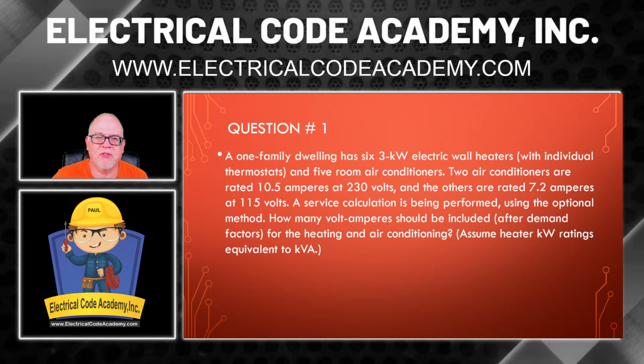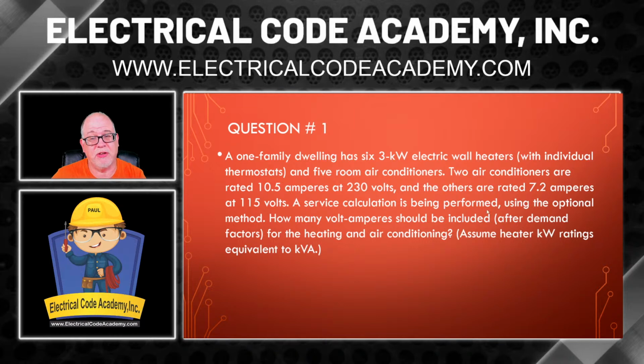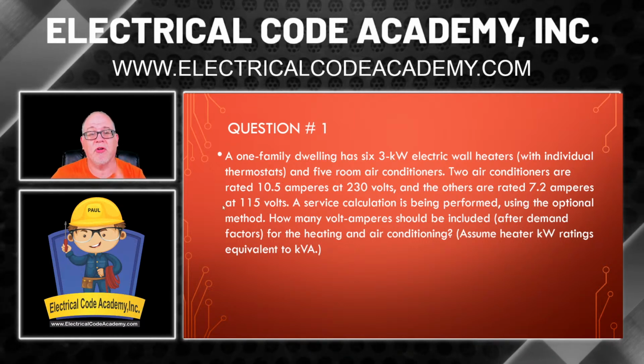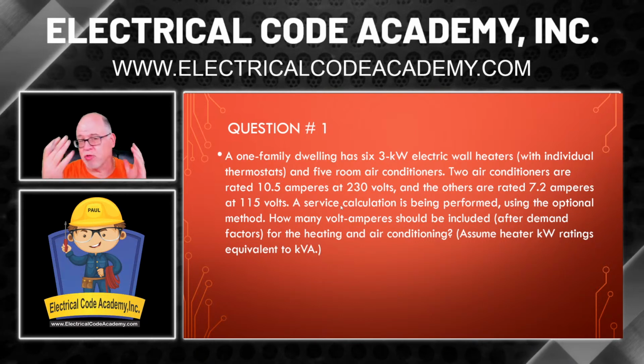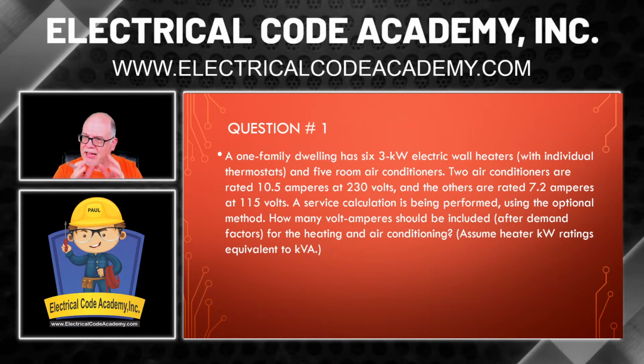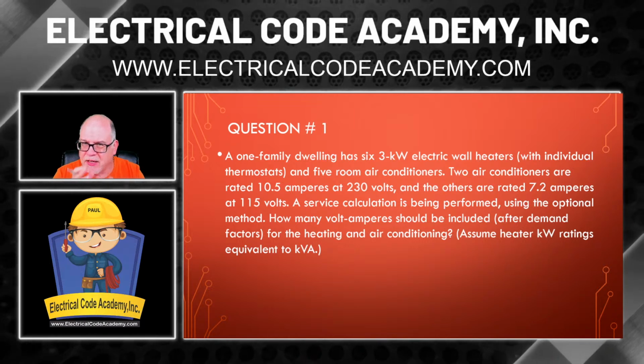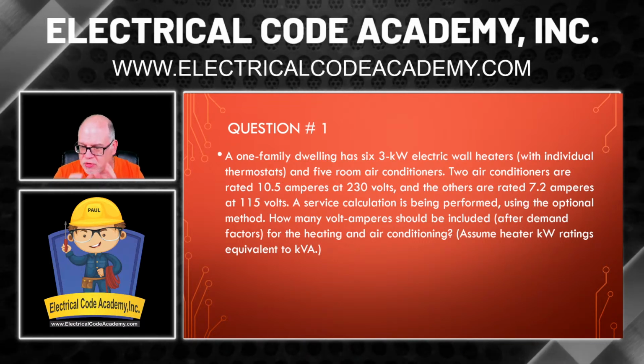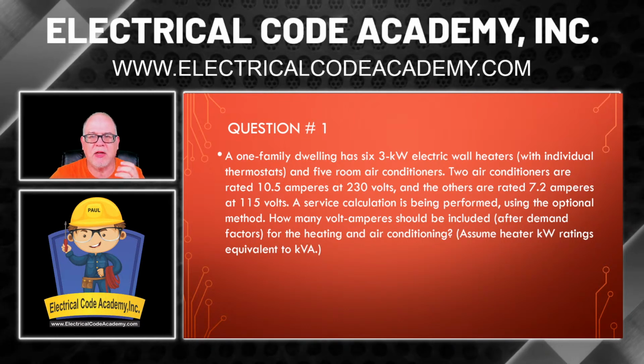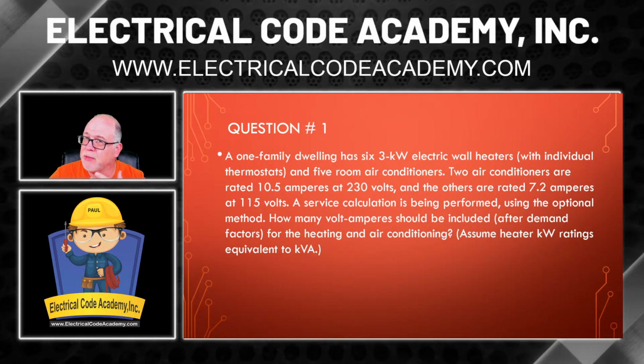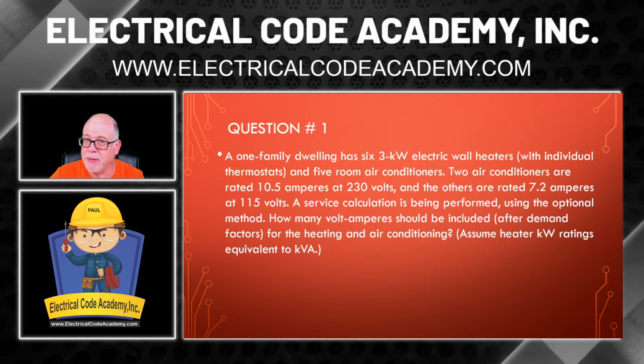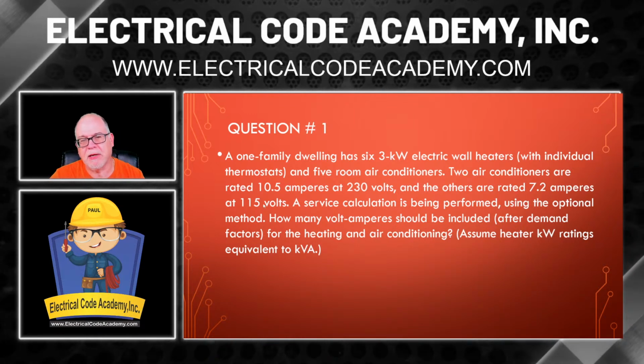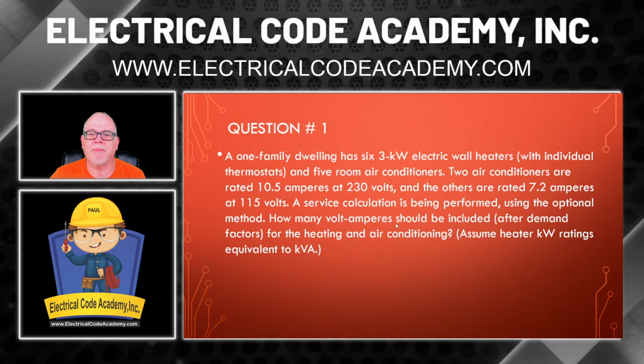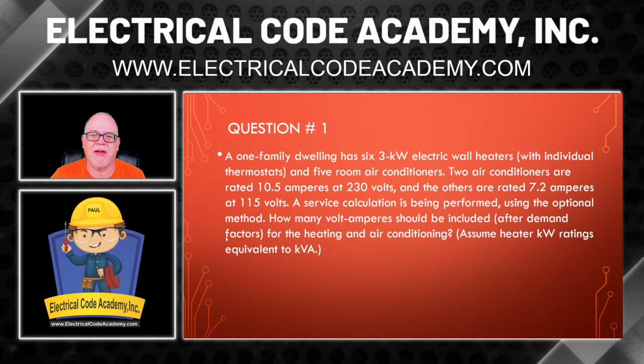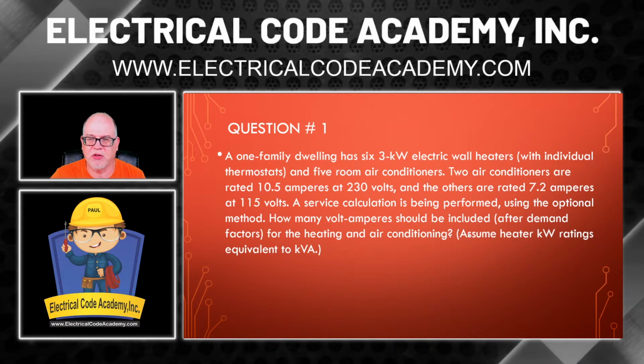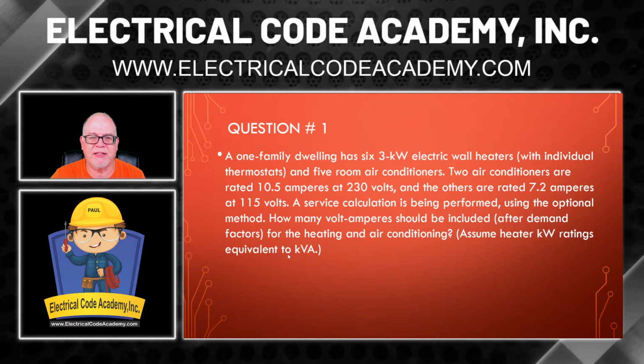All right, now it goes on to say, a service calculation is being performed using the optional method. So they'll be using the optional method to do their overall service calc. But it seems like we're only being asked to do the AC and the heat and compare the two. That's all we're being asked to look at right now. But it is reminding you that they're using the optional method, so that's going to put you in the optional area. That would be Part 4 of 220, right? Okay. Now, how many volt amperes should be included after demand factors for the heating and air conditioning? Assume heater kW ratings are equivalent to kVA.